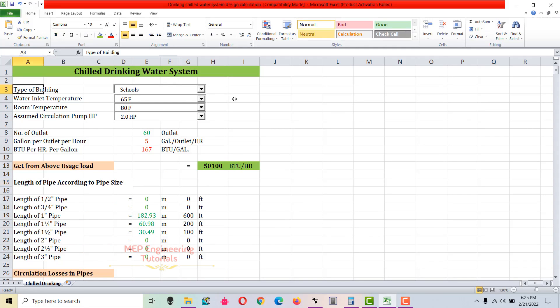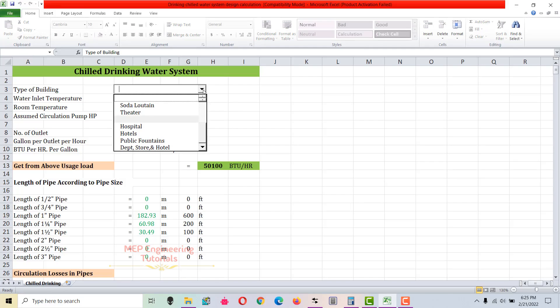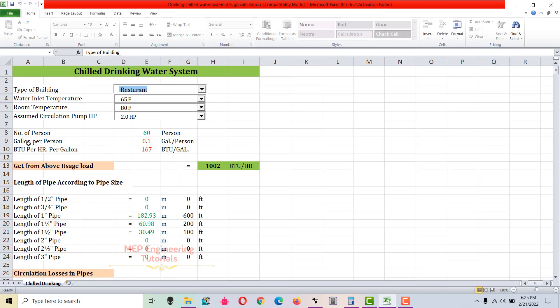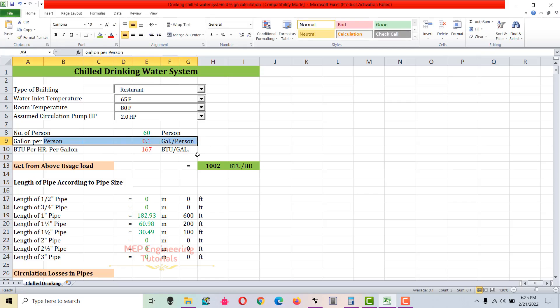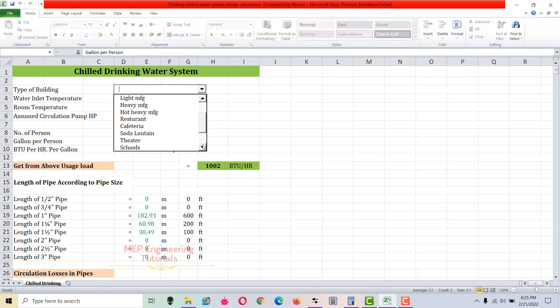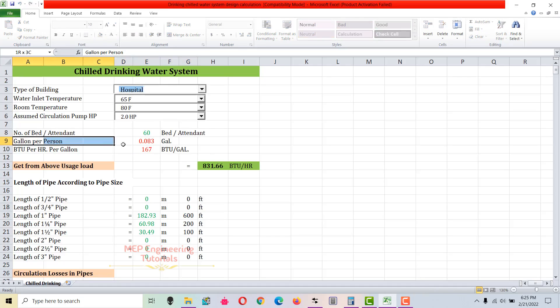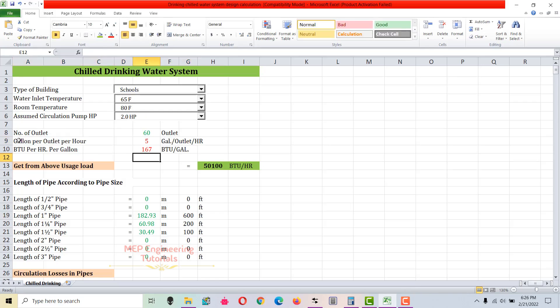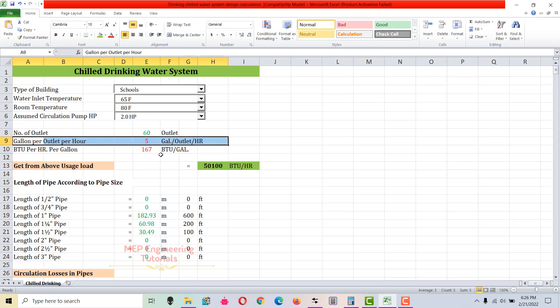First of all, you have to determine the type of building in which you are going to place this chilled drinking water system. You have to select from here the type of building. Based on the type of building — if you select restaurant, gallons per person is 0.1 gallon per person. This value changes based on building type. If I select school, gallons per outlet per hour is 5 gallons.